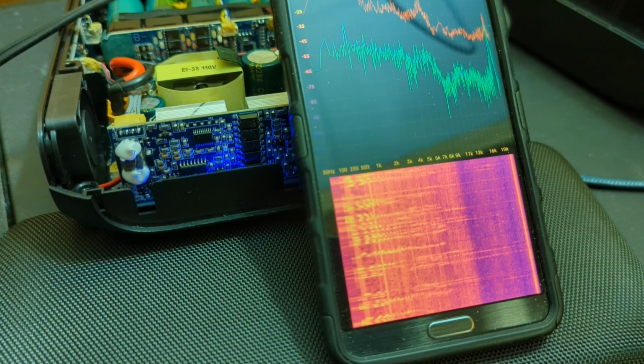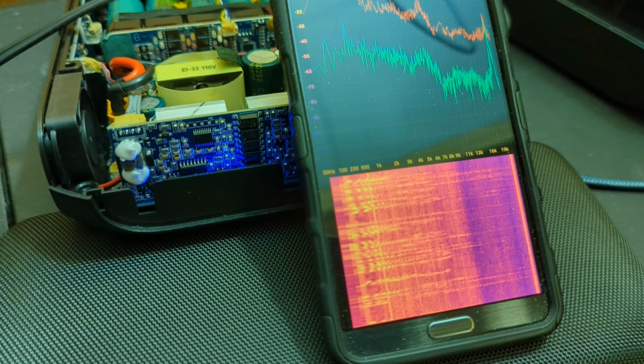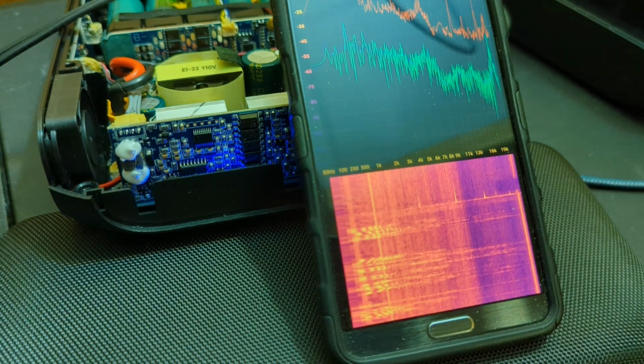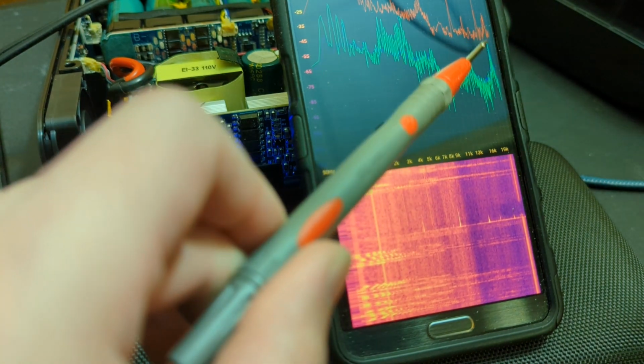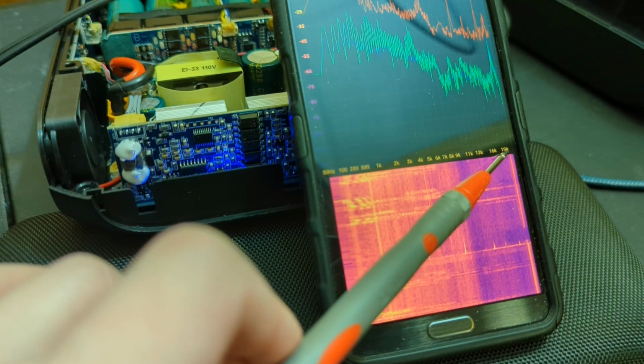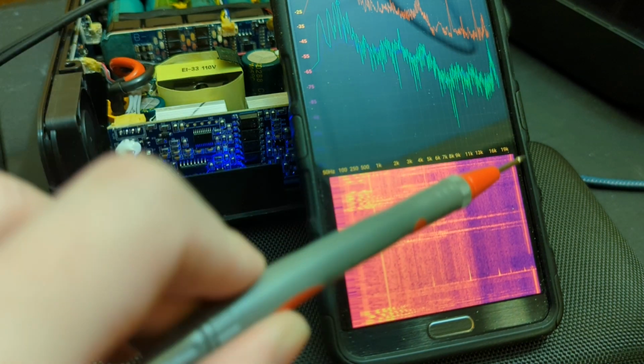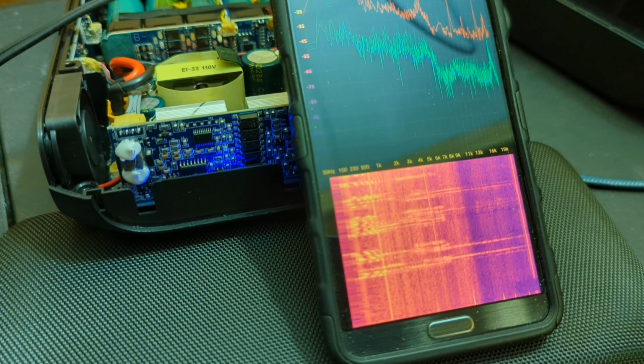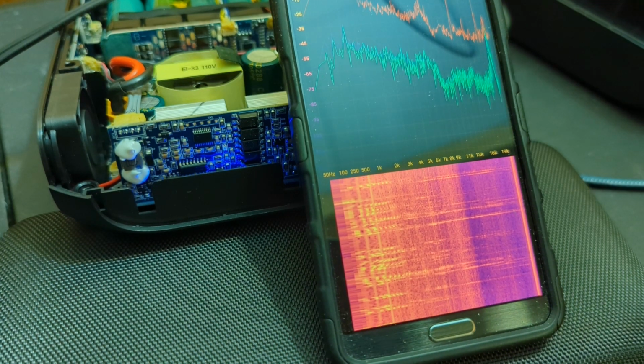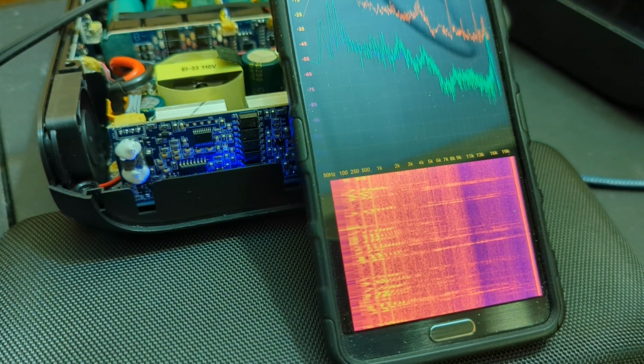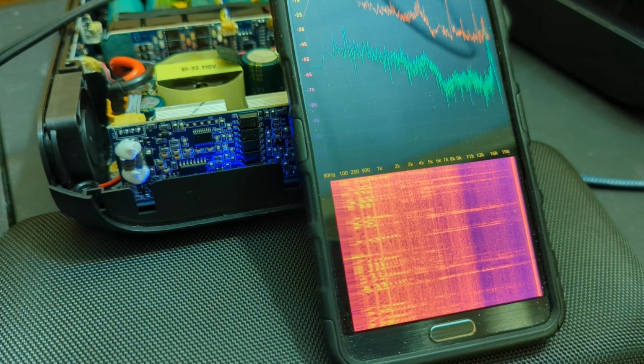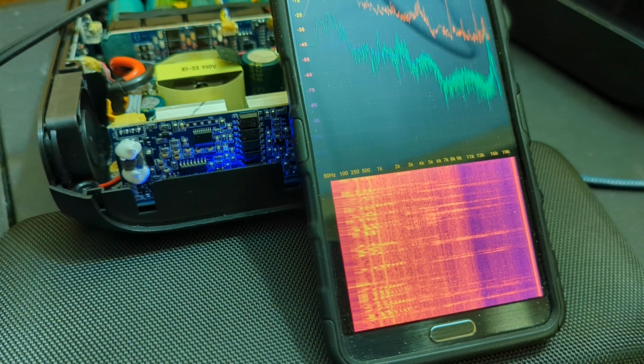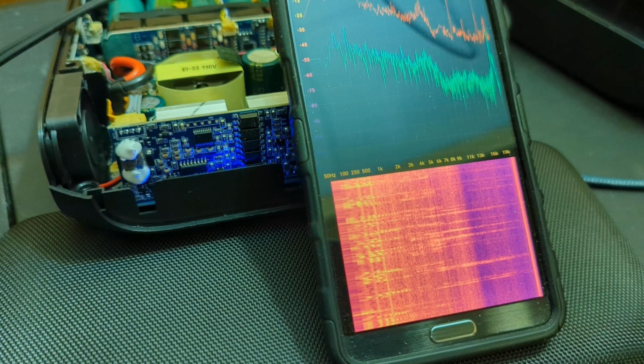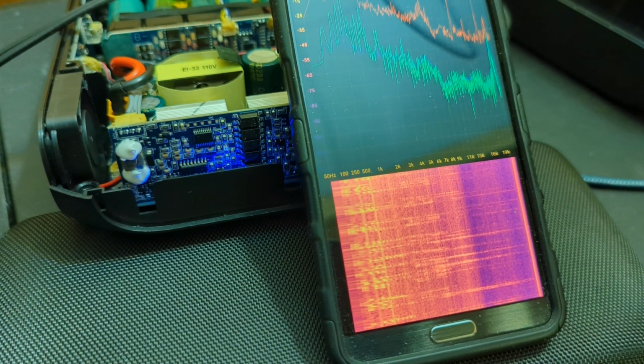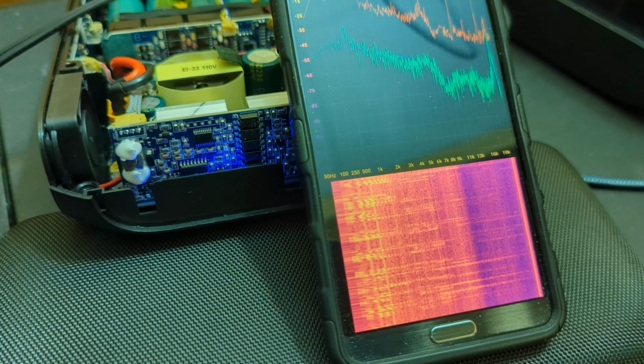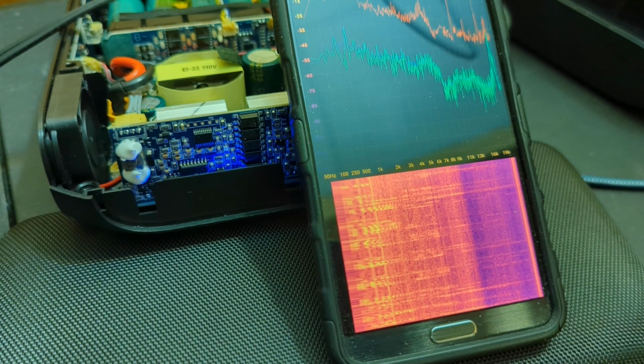You likely won't hear it again because the fan noise is much louder. But if I turn off the load, when the fans stop, you'll see the white line at 19K, the peak is much lower, and the intensity of the noise comes down. Doesn't seem to be a problem. It's really just a circuitry design and the type of PWM switching being used, and whatever power MOSFET or IGBT is in the inverter circuit.